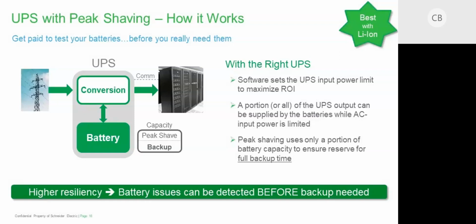One of the benefits of utilizing UPS batteries is, when the batteries are sitting there and not being utilized, you don't know if they're good or bad. But by testing them on a regular basis and utilizing them to do peak shaving, now you can detect whether or not those batteries are good before backup is ever needed. So that's another side advantage that you get with utilizing a UPS with peak shaving capability. Next slide.